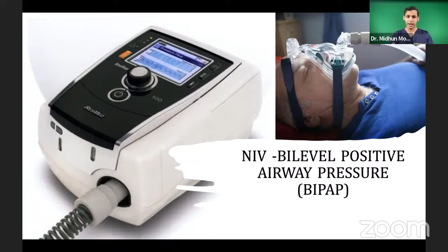Now, how NIV or BiPAP works is somewhat different from a CPAP. In CPAP, the machine was giving a continuous positive pressure. The same pressure was given during inspiration as well as expiration. That was the baseline pressure, elevated from 0 to a positive level. What BiPAP does is keep two separate pressures. One is an elevated basal pressure during expiration, same as the CPAP, called the expiratory positive airway pressure.